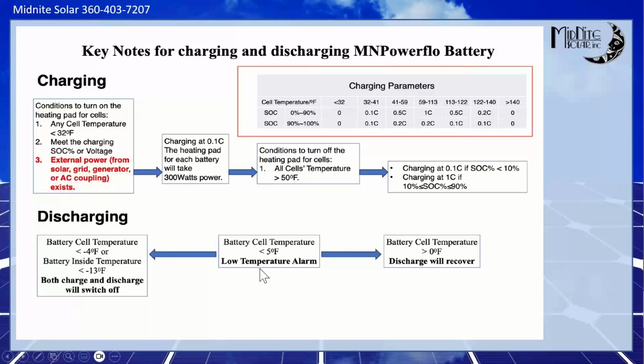Discharging is different, but a little similar. If it's below -4 cell temperature or -13 inside the battery, we'll shut off and throw an alarm, and it will recover when it gets up to 0 degrees Fahrenheit. So discharging is not as finicky as charging on a lithium battery for sure. But this is an important chart to get your hands on. I can email it to anybody that wants it if they want to shoot me an email. This is just something that's good to have.